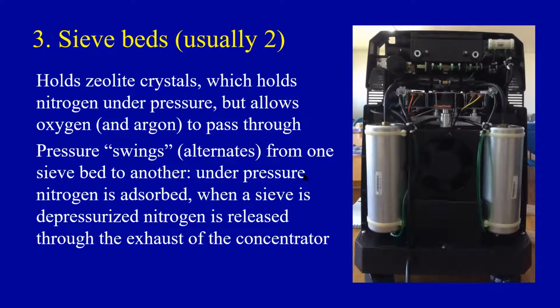And that means when the gas is flowing into this one, it's making pure oxygen, and then the gas flows out, and then the machine turns to the other one, and gas flows through here and makes pure oxygen. So the pressure alternates between one sieve bed and the other sieve bed, and that's why the concentrator makes the alternating noise that you hear.